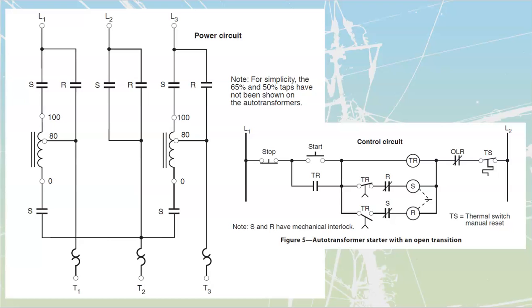You'll note that we've got a couple of components that we are familiar with. We have got time delays over here. One of these is normally closed and timed to open. The other one is normally open and timed to close. But you'll note that both of them are going to be fired by the same one. This one is going to pop open. This one is going to pop closed. But for a brief second, while this one is opening and while this one's closing, neither one of these is going to be closed. It's going to be so fast we're hardly going to notice it, but it is going to be an open transition as a result of this.